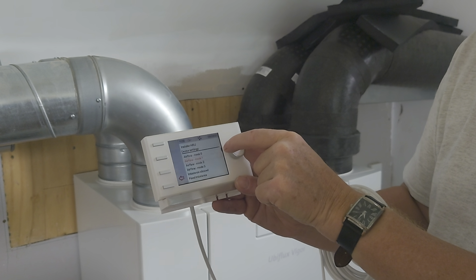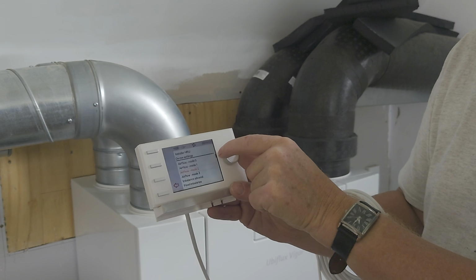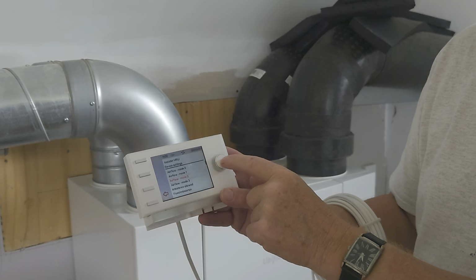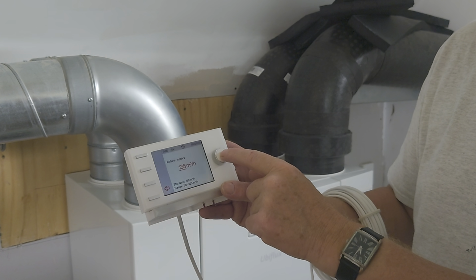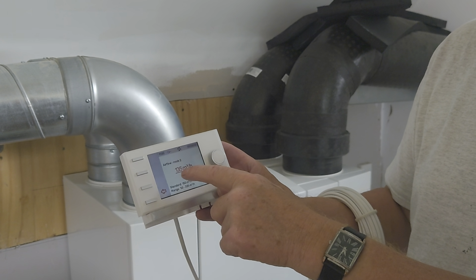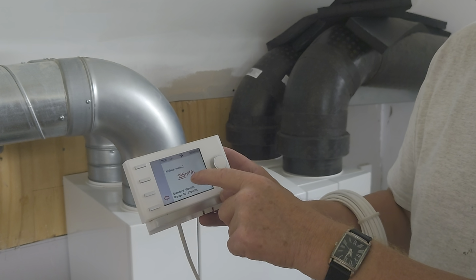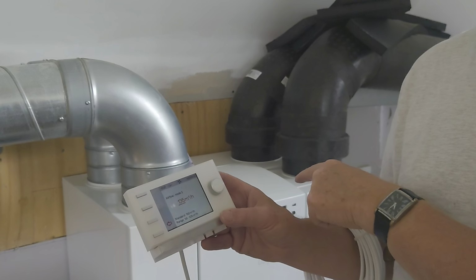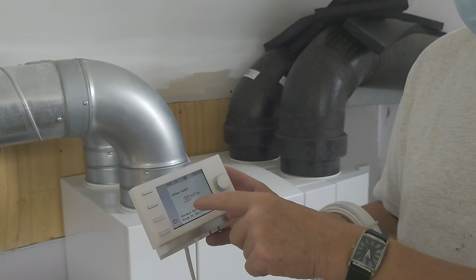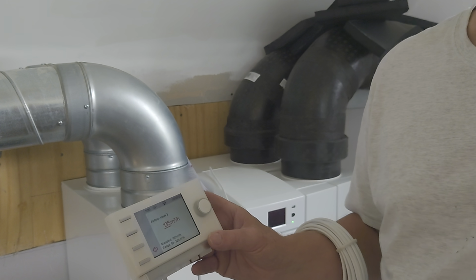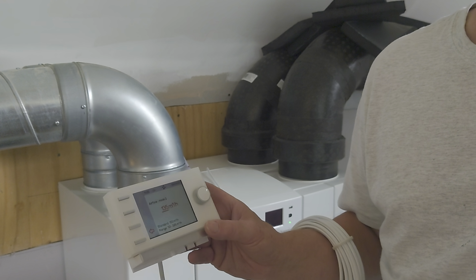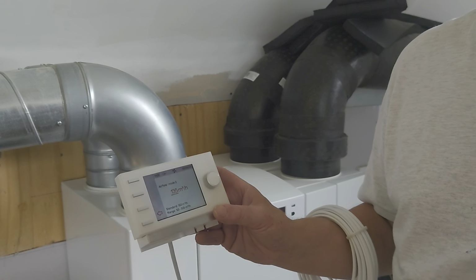So those are 4 airflows - I've set those to the design levels. On speed 2 it's 135 cubic metres an hour, and this unit is capable of 325. So on your normal running speed, it's just ticking away nicely - you'd never want to run one of these things full whack.